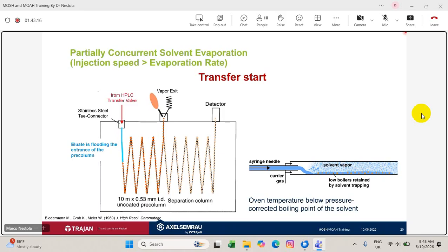You lost everyone. Okay. So, first of all, closed. We are getting our carrier gas from the top. So the carrier gas is flowing through our columns. It's closed here, so it cannot exit, and it is just reaching the detector.